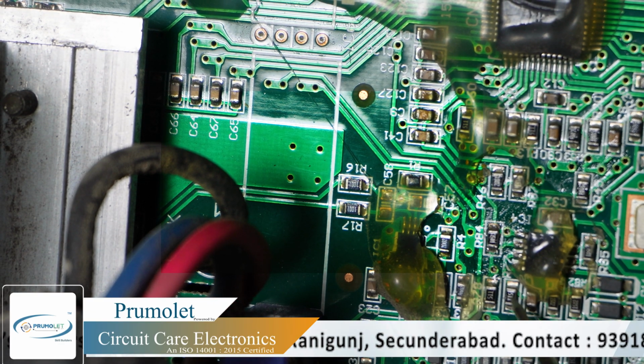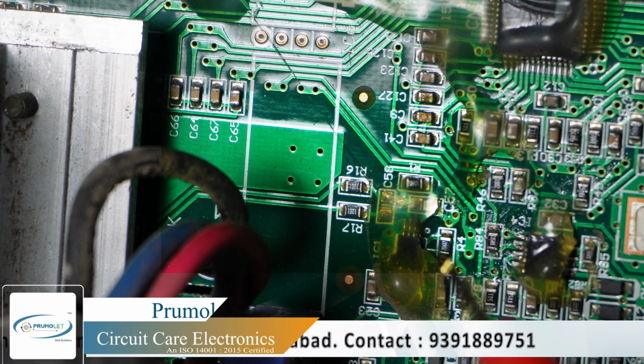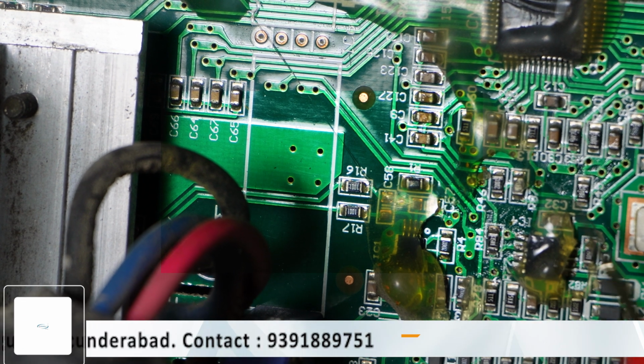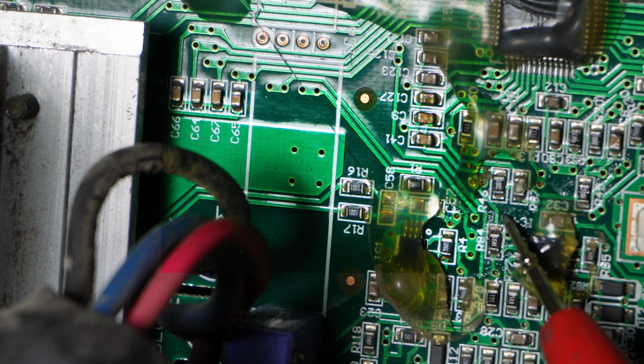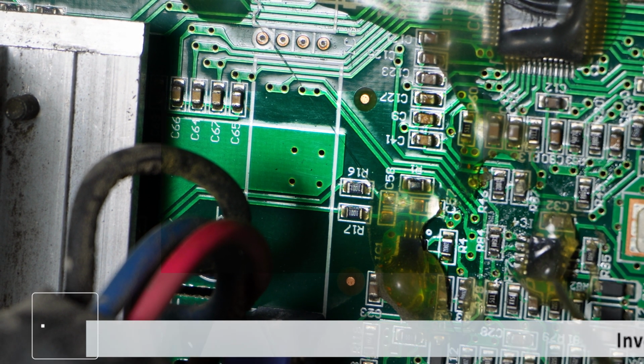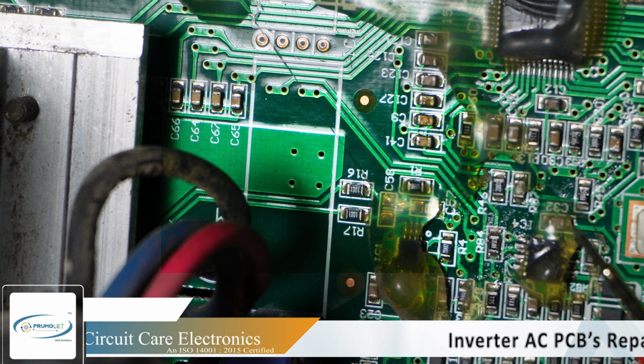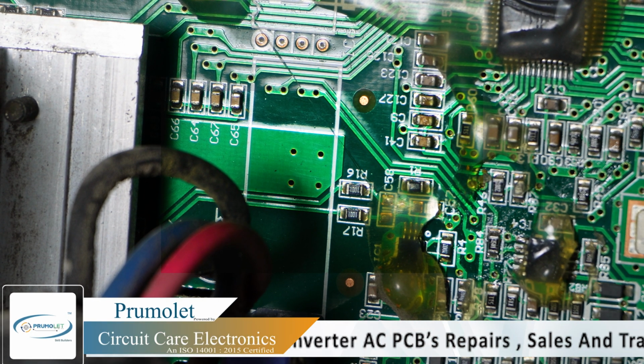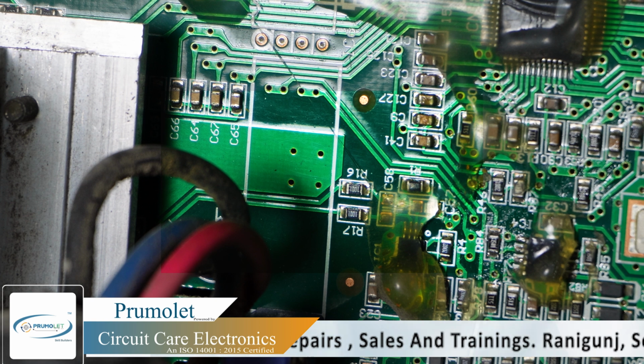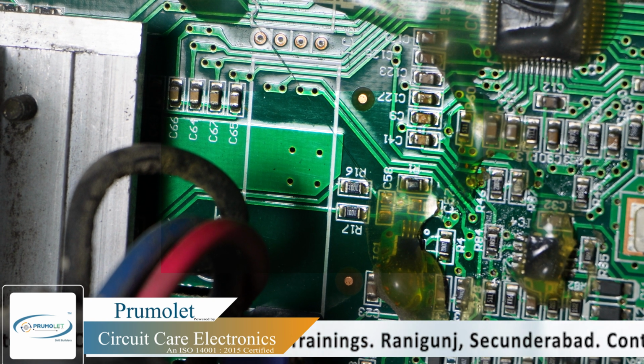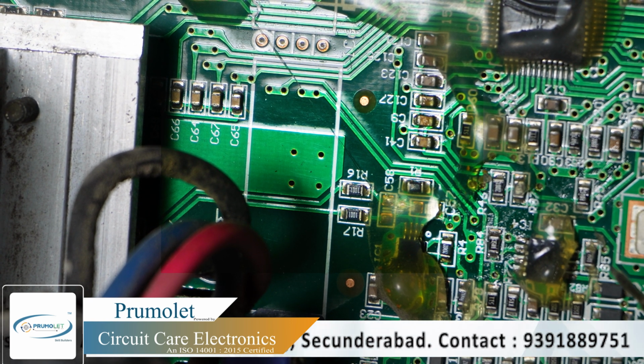Now this comparator is for both AC and DC voltages. This resistor is failed, due to which the reference voltage is showing wrongly. When the reference voltage is wrong, the PFC will oscillate more. That's why the overcurrent error is coming.